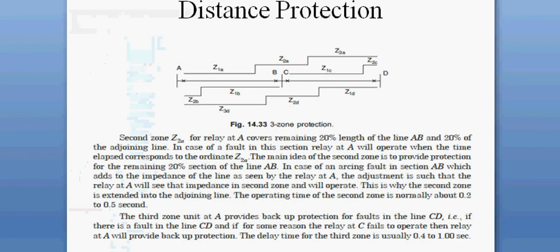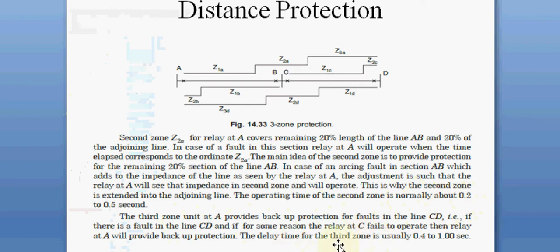This is the entire case of distance relay protection. The time of operation in Zone 2 is 0.2 to 0.5 seconds, and in Zone 3 the time delay is 0.4 to 1 second.